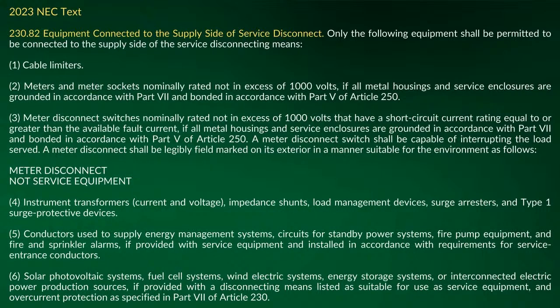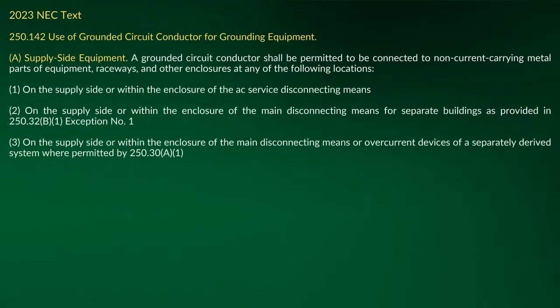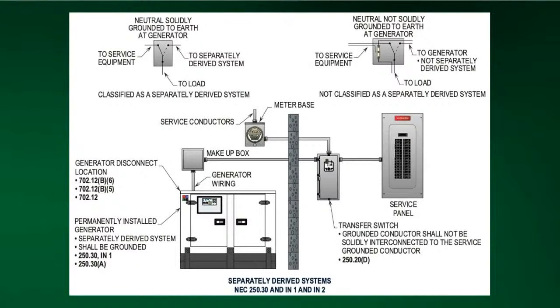I have a Generac system that's set up at a house, for instance, and I've got the Generac generator sitting out there on the pad on the ground, and then I've got my ATS, my automatic transfer switch, up here mounted on the wall. And right before it, if you look at 230.85, I have an emergency disconnect out there. Okay, now this is where it gets interesting, because I'm going to show something here and I'll come back to it, but we have some good illustrations on this particular point. Hold on a minute. I just want to interrupt you a little bit, James.